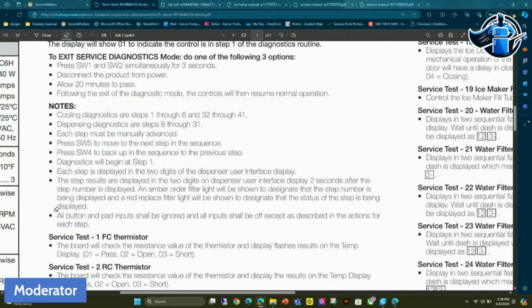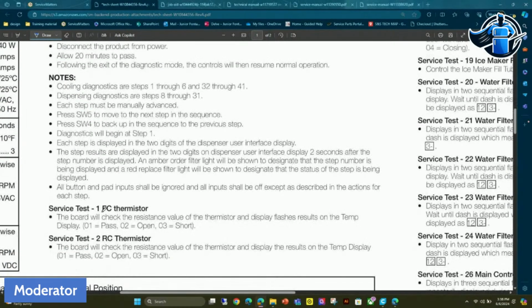We'll cover this as we do it on the unit itself. I want to call this out because it's something customers ask about a lot. Why is there a red replace filter light on my unit when you're in diagnostics? I already replaced my filter. That's how you tell the difference between being in a test and the result of a test, along with the results flashing as well. Whirlpool added that feature because some guys do miss those.